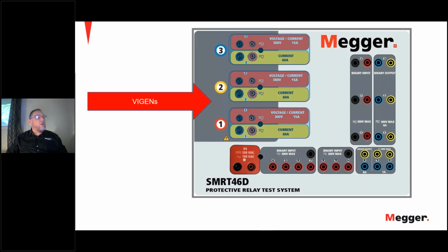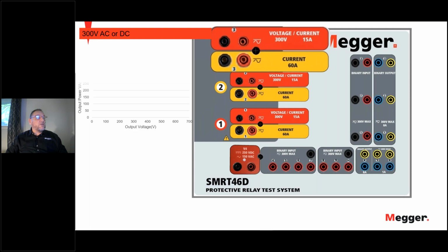Okay, moving on. First of all, in a 46 unit, you've got what we call 3 Vigens, and a Vigen is a voltage and a current generator. On the Vigen, the red side is your voltage channels with, again, the maximum output of 300 volts and 150 VA, as shown in this red power curve. Several voltages can be connected in series to provide a higher voltage and power output, as shown on the green curve on the screen.